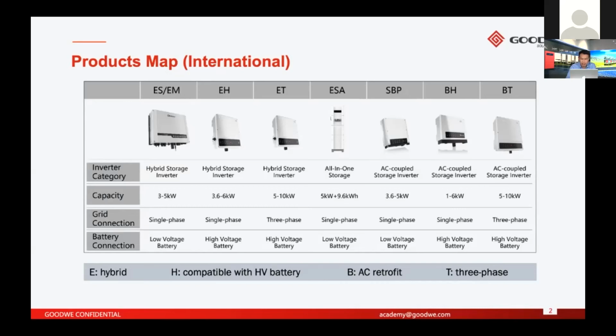Another part is AC coupled. AC coupled means model names that have B, like SBP, BH, and BT. AC coupled means it cannot connect solar. The general difference from the hybrid is that it cannot connect PV systems. It only has grid connection, off-grid loads, and battery. So normally AC coupled inverters are used with on-grid systems. It's not used alone, all right?